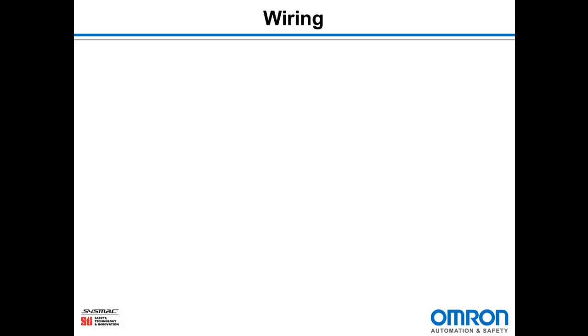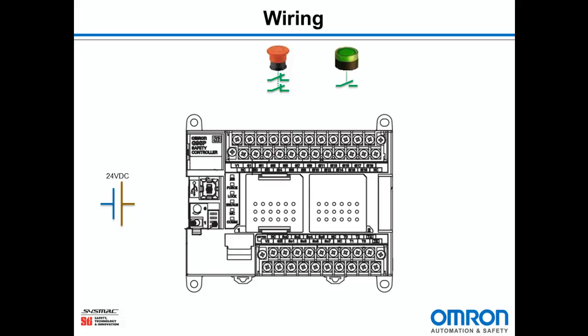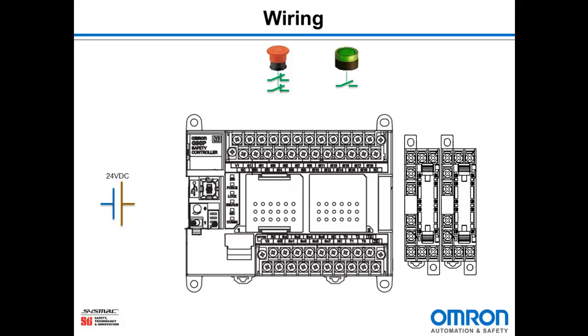So let's talk about wiring. Today I'm going to build a simple safety circuit that replicates the functionality of a safety relay. We're going to have a G9SP, a 24 volt DC power supply, an e-stop button with two normally closed contacts, a reset button with one normally open contact, and two G7SA force-guided relays with auxiliary normally closed contacts.